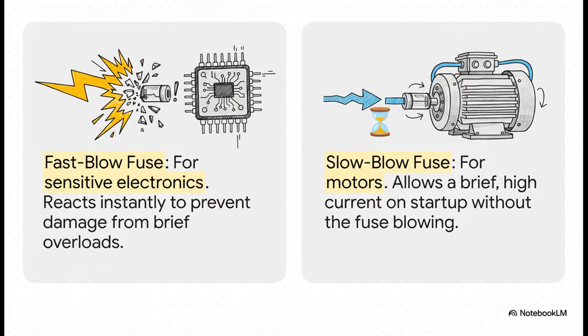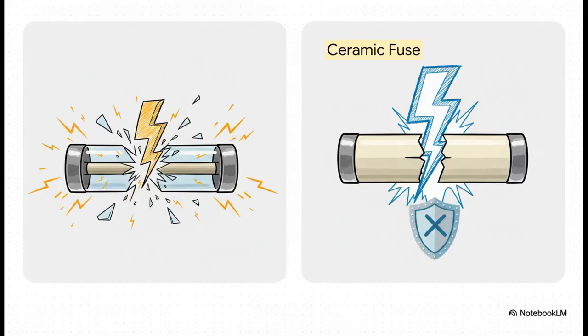First off, you've got to think about speed. You've got fast blow fuses, for super sensitive electronics that'll get fried by even the shortest power surge. But if you put one of those in something like a power drill, it's going to pop every time you pull the trigger, because motors need a huge jolt of current just to get spinning. For that job, you need a slow blow fuse. It's smart enough to ignore that initial startup surge, but it'll still blow if there's a real sustained problem.